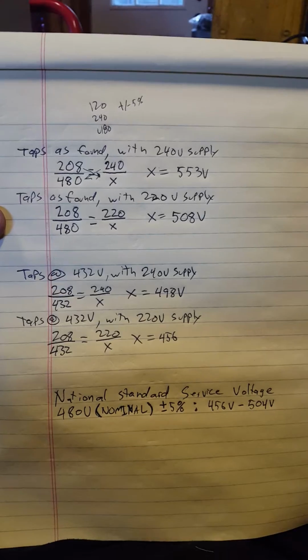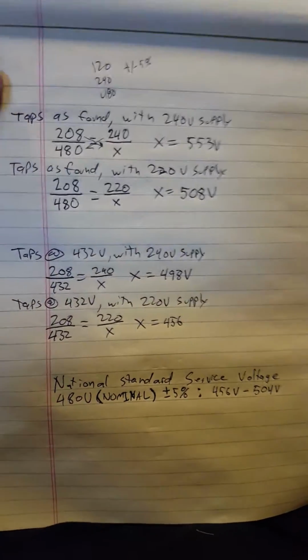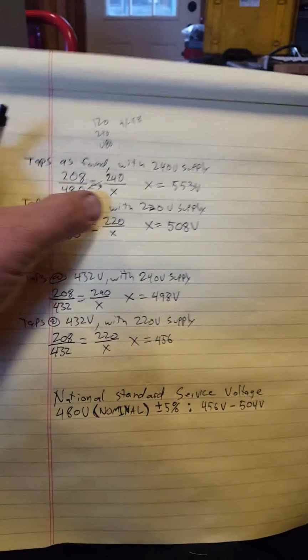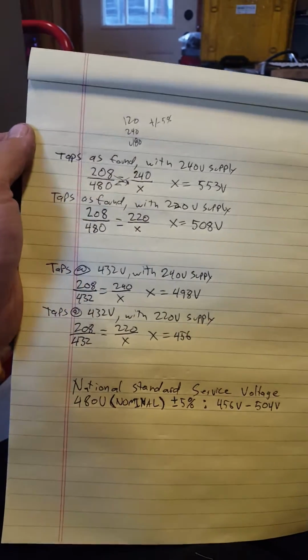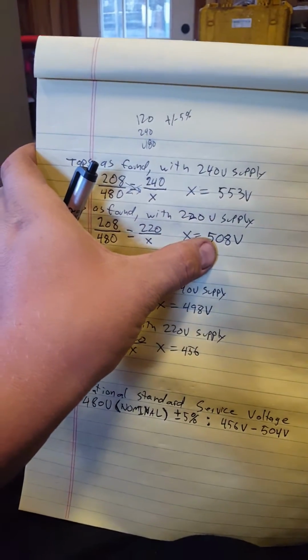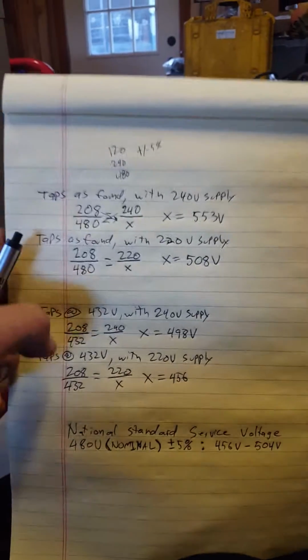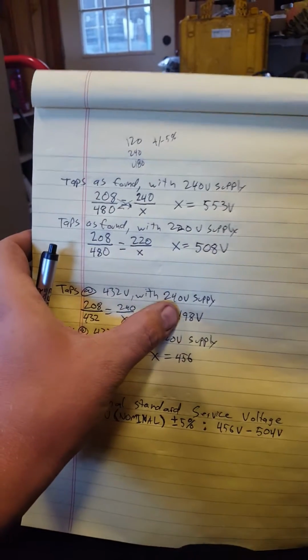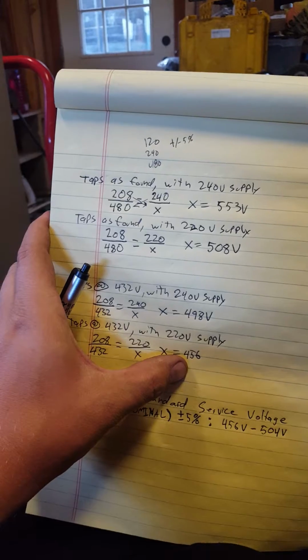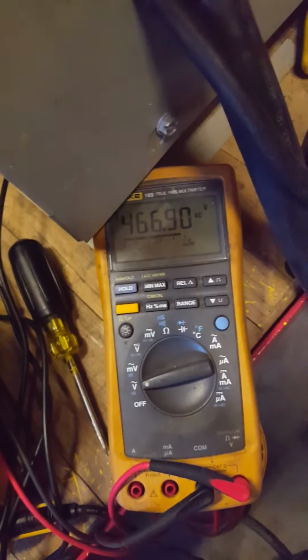So I did some math too. Let's check out the math. The reason why I'm getting away with this 208 volt transformer is because if you remember, when I measured the incoming voltage, it was like 220, which is below the national service nominal voltage. It should be 240. With the taps as I had them before I just changed them, if I were to apply 240, I'd get 553 volts. But with 220, I only got 508, which is pretty close to what I measured. Now, after moving the taps to 432 volts, with a 240 supply, I'd be at 498. But with a 220 supply, I'd be at 456. 467, yeah, we're pretty close.